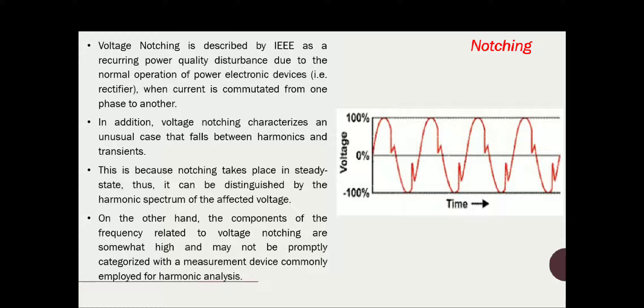Since notching takes place in steady state, we can distinguish it by the harmonic spectrum of the affected voltage. On the other hand, the frequency components related to voltage notching are somewhat high and may not be promptly categorized with the measurement devices commonly employed for harmonic analysis — that is, we cannot categorize the frequency components using devices typically used for harmonic analysis.